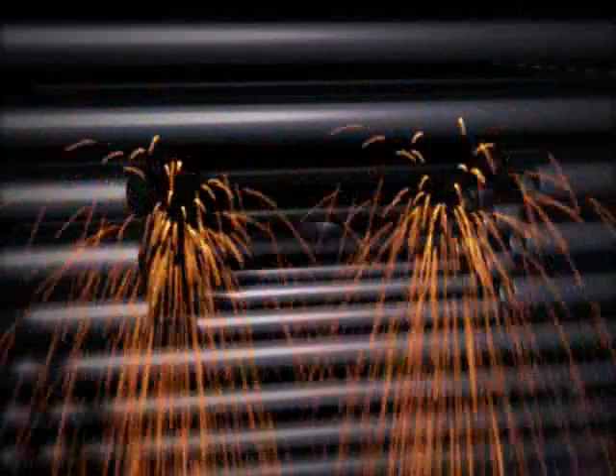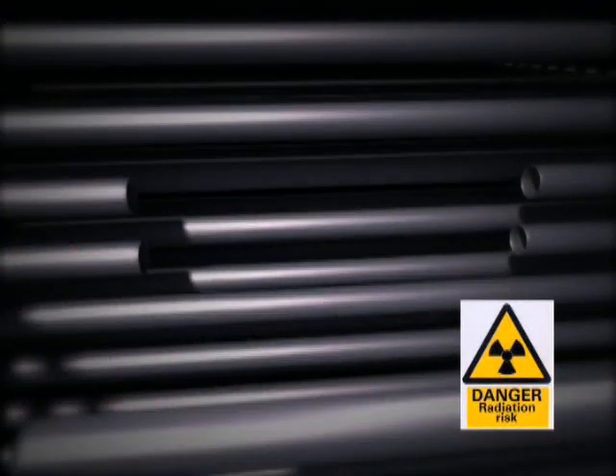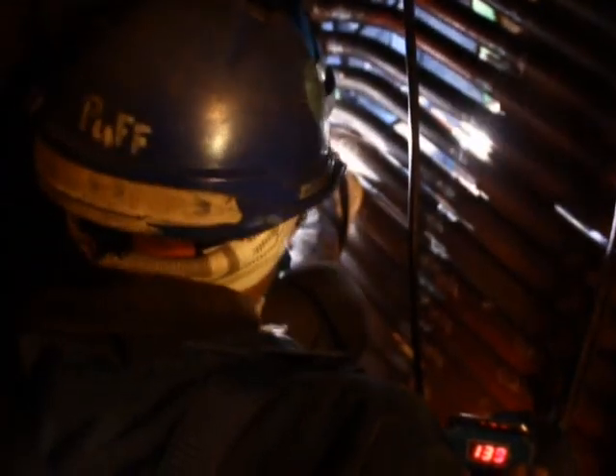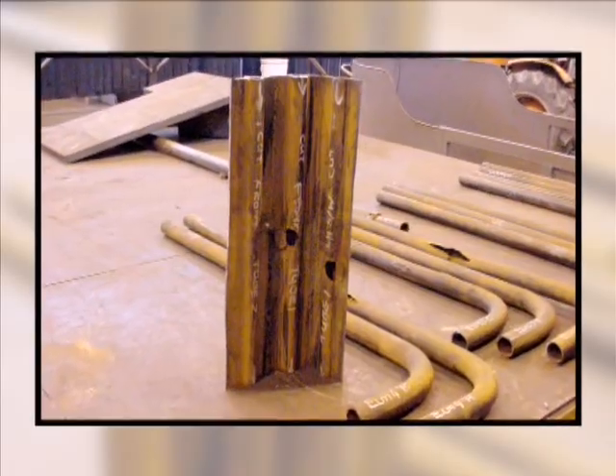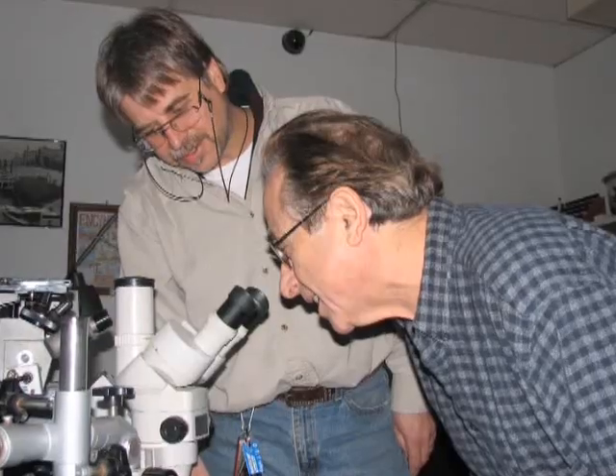The quality of the repairs is of utmost importance. Each weld is X-rayed, and the X-rays have to be signed off by a competent person. If the X-rays reveal defects in the welds, the tube is cut out and re-welded, and the quality checks have to be repeated. Tube samples of the failed tubes are sent to our metallurgical laboratories to confirm the failure mechanism. The inspection authority, acting on behalf of the factory's inspector, has to apply his stamp of approval to all work carried out on the boiler.